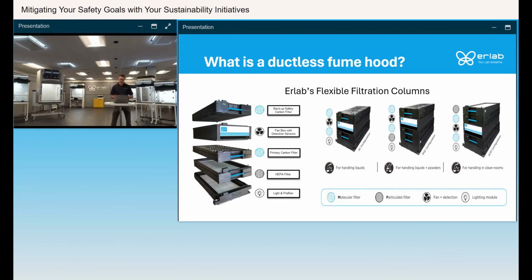So over on the right side, you can see the different configuration of the filters. It's about 50-50 now, whether it's just carbon filters, where you would just need the primary carbon filter and a backup carbon filter on each filtration column, or if you need to add a HEPA filter, again, for using toxic powders or any exothermic reactions. But that flexible filtration column also allows you to install these hoods in clean rooms because you can have the HEPA filter on top of the last carbon filter, and that helps you keep the particle integrity count of the clean room. So basically ISO 7 or cleaner.